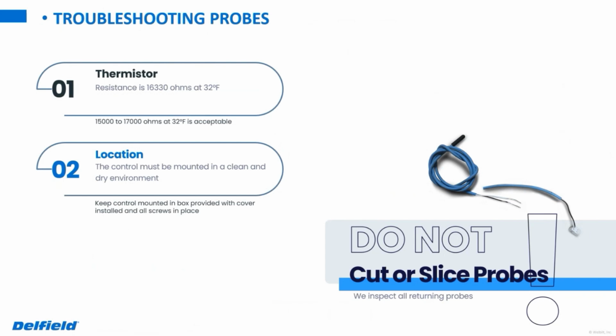All right, so as far as probes go, in the past on the controls that didn't have the ability to go in and check those probe readings, we would have you check resistance on those. Not really something that we're doing a whole lot anymore, but it still has a little bit of value as far as just determining if the probe is okay or not. A lot of times if you do check that, the resistance on those is going to be about 15 to 17K at 32 degrees.